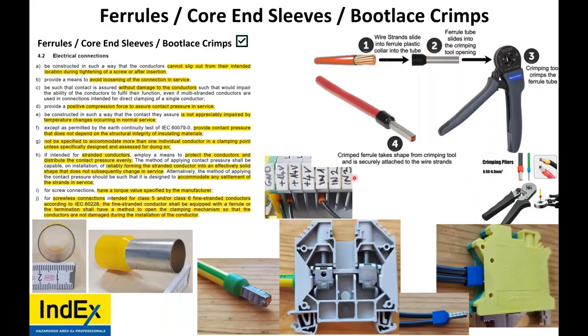Now, how easy is it with a ferrule? Well, strip it, twist it, slide it on, crimp it. I can install these in one third the time of an insulated pin crimp. So anybody that says it's about cost, well, man hours cost a lot more than 1,000 little pin crimps. Once again, here's a 16 millimeter, and it slides nicely into the terminal. There's the inside of the terminal, and it makes flat to flat surface contact. Low resistance, good quality connection, right the first time.